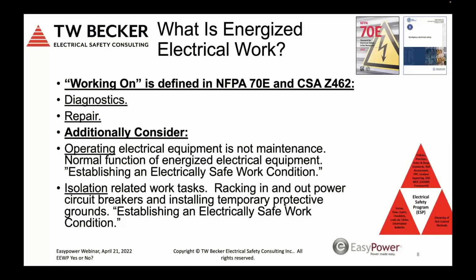and isolation-related work tasks, which are not maintenance work tasks. They're specific to isolating electrical equipment. And under operating in isolation, I've noted, part of the establishing electrically safe work condition procedure, that's also another important element of 70E and Z462, requires operating electrical equipment and doing these isolation work tasks of racking in or out low voltage power circuit breakers or high voltage power circuit breakers. Again, and for high voltage, installing temporary protective grounds.